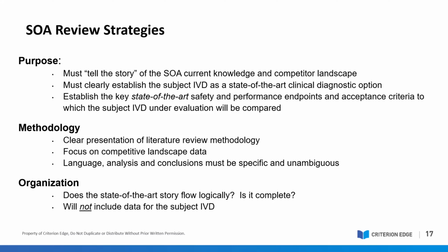And that can include referring to standards that have been used for same or similar devices, but you have to know what those same or similar devices are. It can also include things like best practices as used in other devices of the same or similar type, and the results of accepted scientific research. That's a big part of the searches you will conduct in order to establish your competitive landscape.